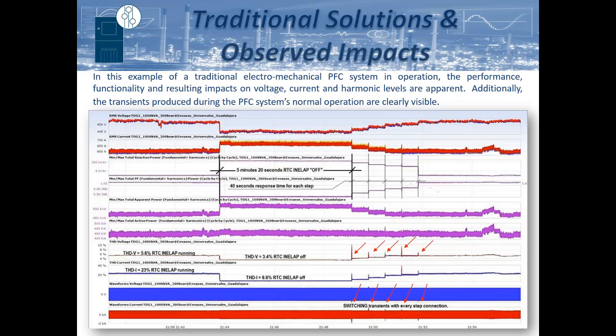So some of the traditional solutions include power factor correction, where these systems operate on an electromechanical contactor basis, and the primary purpose is just to correct for the power factor, which is advantageous for utilities and in order to get rid of any associated penalties that may be incurred. But there are a lot of negative aspects that, if the system isn't designed properly, can have a negative impact. And on this one right here, you can see that we had a traditional power factor correction system engaged, and then we turn the system off for a little over 5 minutes and then re-engage the system.